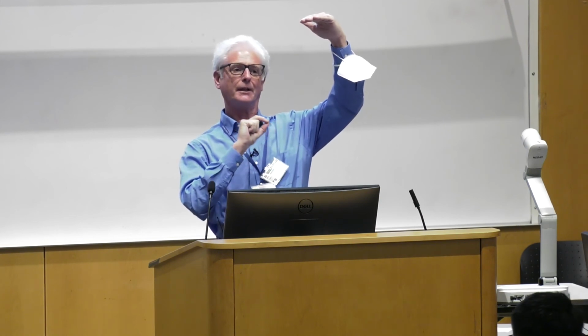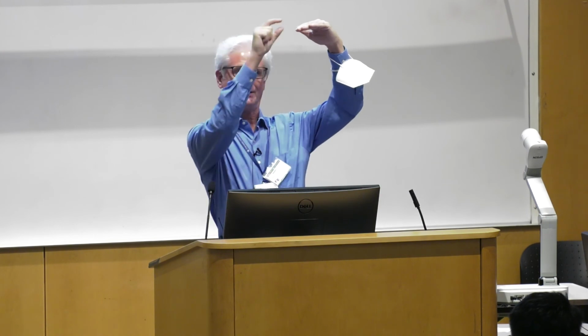Another way in which people look at linearity is, if you can get three power levels, you can also put in a glass plate, and that will give you a fixed delta in your transmission. So you'll have power at three levels and then a small delta at each of those levels, and you can check that the delta is the same at all three power levels to check the linearity over range. Ideally you do all of those, but sometimes you run out of time.